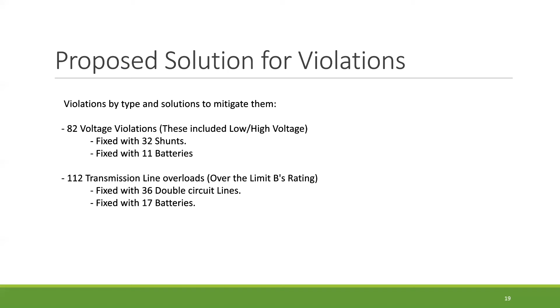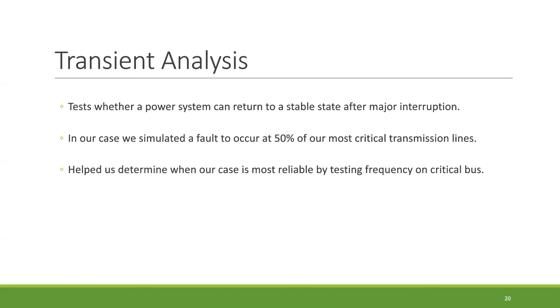Transient stability is the ability of a power system to return to normal after suffering a large disturbance. The large disturbance that may occur is the removal of a load, line switching operation, fault occurring in the system, or a sudden outage of a line. In our case, we tested 3-phase faults on major critical lines. The faults we conducted were for 4 cycles or 0.067 seconds at 50% of the transmission line. The duration of the fault was chosen based on a similar case done by WECC, which they called their standard disturbances.